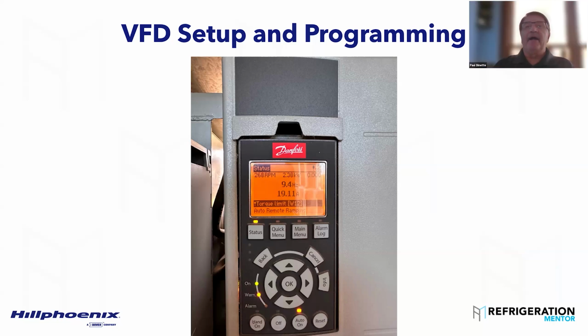Well, the ones off the top of my head are, you want to make sure that on your 1-2 settings, the screen display is set up correctly. On your compressor program, you want to make sure you have the right horsepower, the right amperage, the right voltage, the overcurrent, and that's what you're seeing right there, that torque limit. Whoever programmed the torque limit to 100. It was at 100, not 300%.